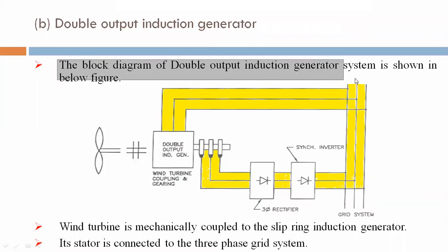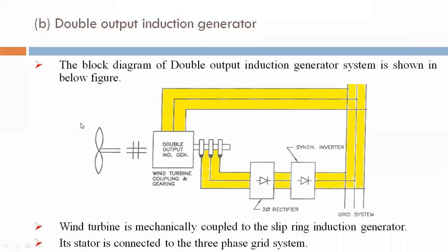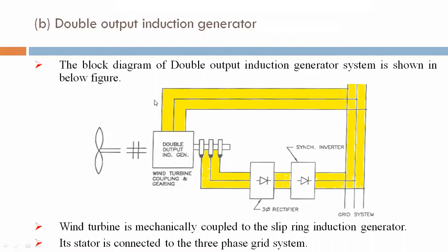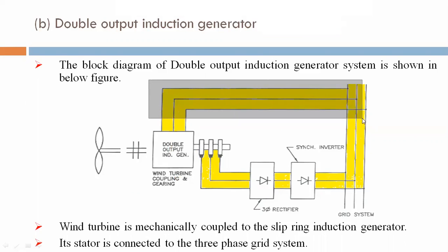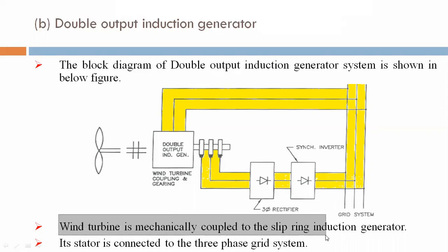The block diagram of the double output induction generator system is shown in the figure below. This is the wind turbine coupling system. The double output induction generator is connected via coupling and gearing system. One supply goes directly to the grid, and here a slip ring of the induction generator is present, through which the signal is rectified and converted by a synchronous inverter, and fed into the grid system via AC.